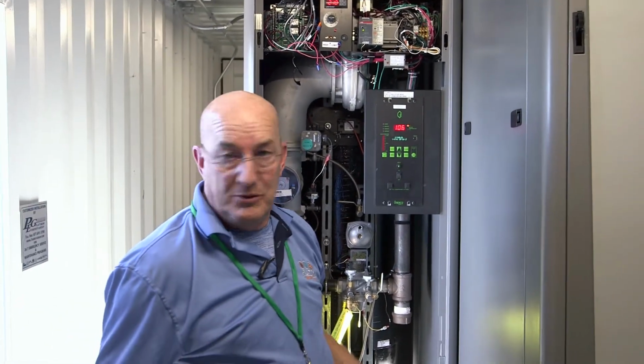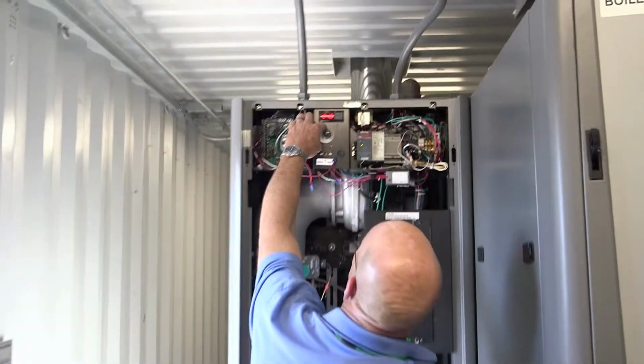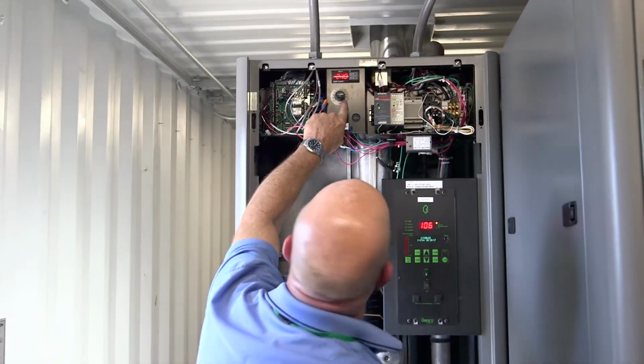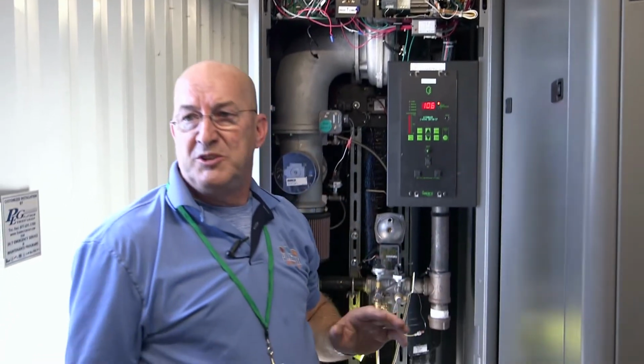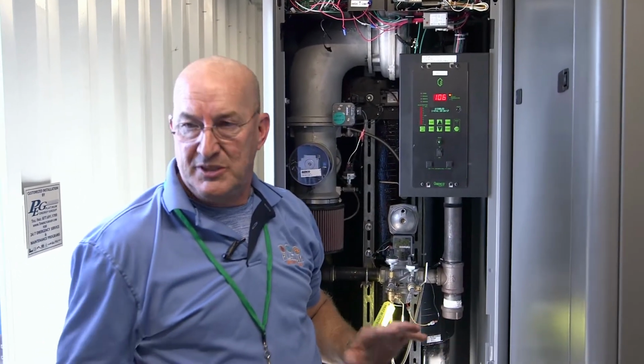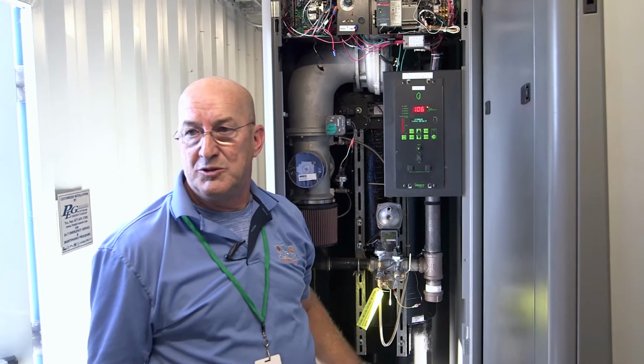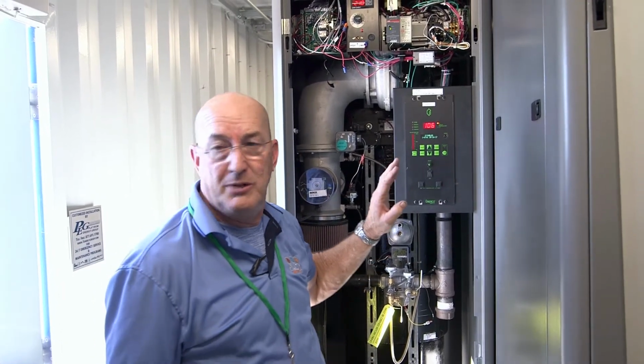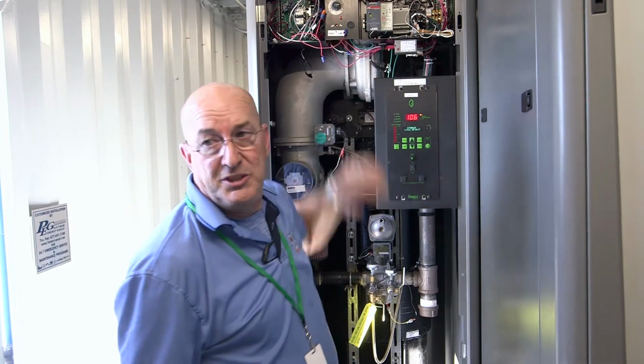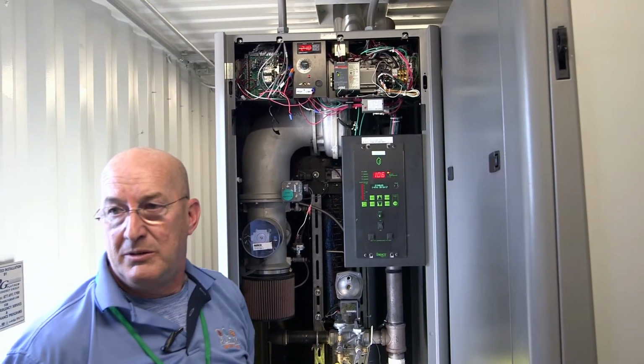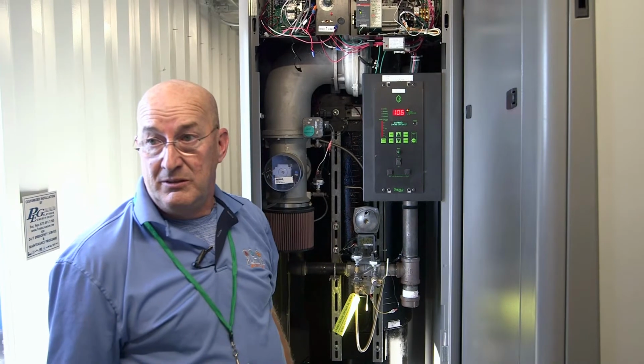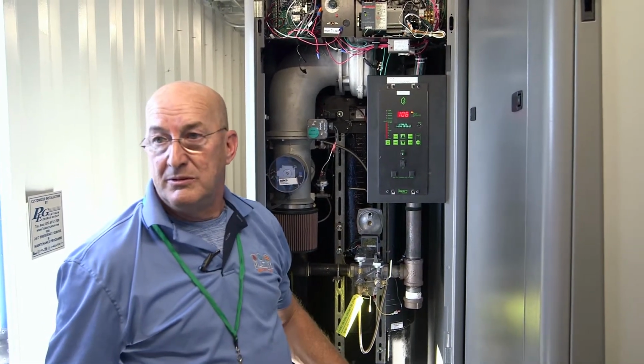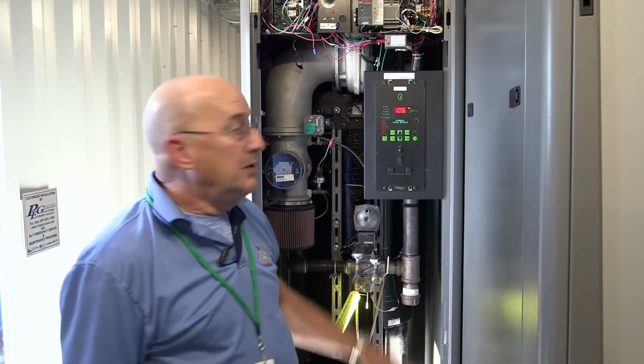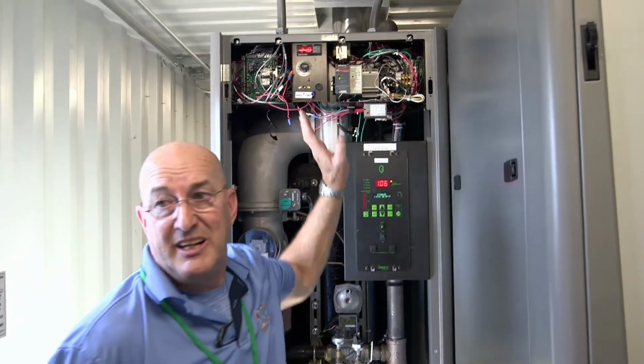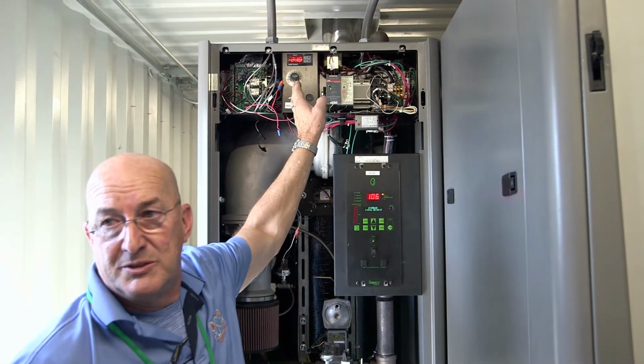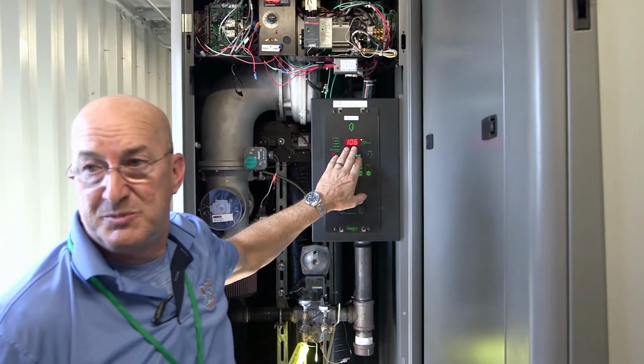You walk over and you look at it, you say, okay, what's the temperature set at? Here we go, here's the notch, it's set at 210 degrees. Nobody touched it, it's where it's supposed to be. 210 degrees is where it should be, never lower, because it's only a safety for high limit. Once you see it's at 200 degrees, you hit the reset button, let the boiler fire up again. If it comes up and shuts off again, now leave it off and call for help. This is only telling you what it's set at. It's not telling you what the temperature of the boiler is. The temperature of the boiler is right here on this display screen.